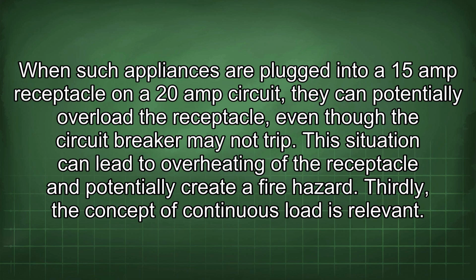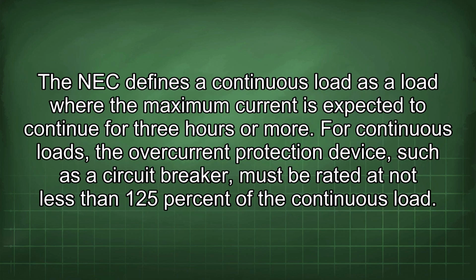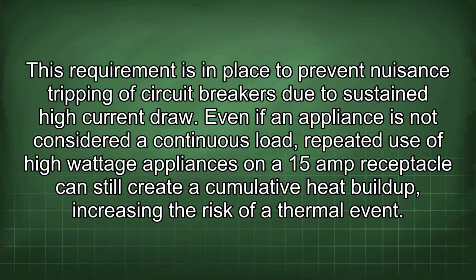Thirdly, the concept of continuous load is relevant. The NEC defines a continuous load as a load where the maximum current is expected to continue for 3 hours or more. For continuous loads, the overcurrent protection device, such as a circuit breaker, must be rated at not less than 125% of the continuous load. This requirement is in place to prevent nuisance tripping of circuit breakers due to sustained high current draw. Even if an appliance is not considered a continuous load, repeated use of high wattage appliances on a 15 amp receptacle can still create a cumulative heat buildup, increasing the risk of a thermal event.